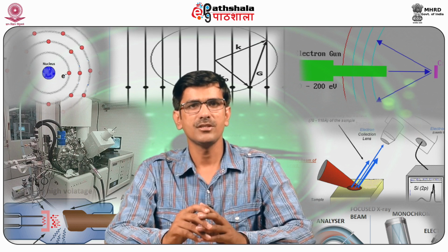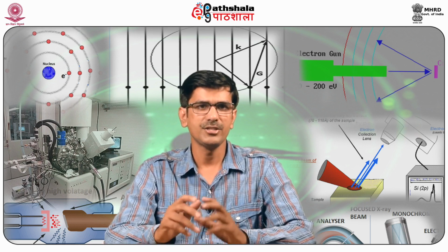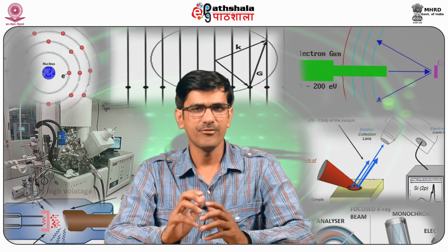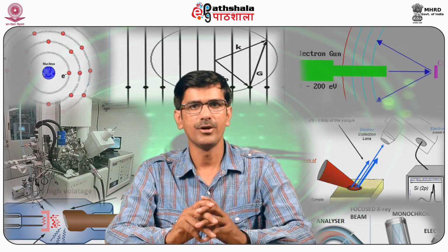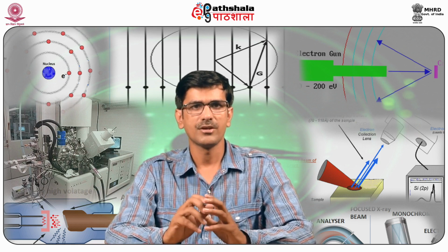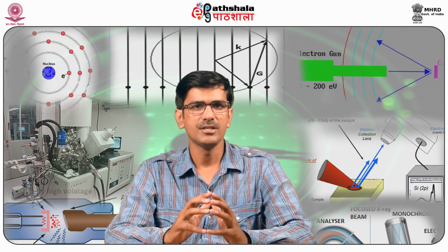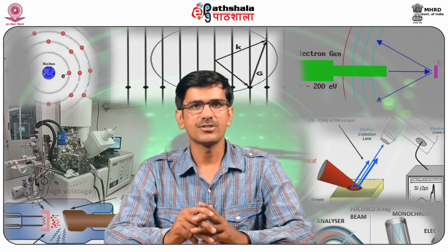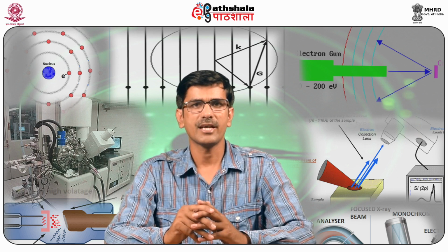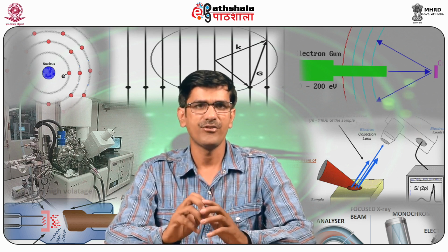The diffractometer circle, also known as goniometer circle, is centered at the specimen, whereas the X-ray source and the detector lie on the circumference of the circle. A goniometer is like a high-tech sample holder. It serves to hold the crystal in the beam of X-rays, but it also rotates the sample to a precise degree.